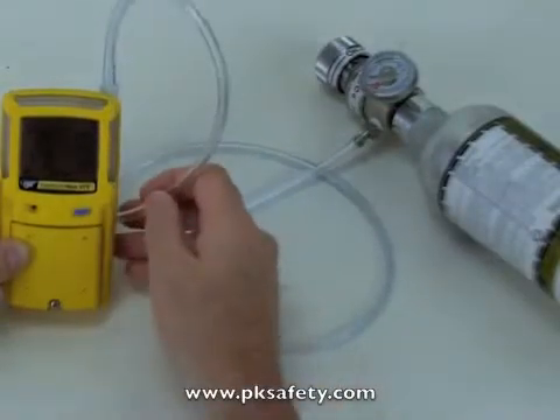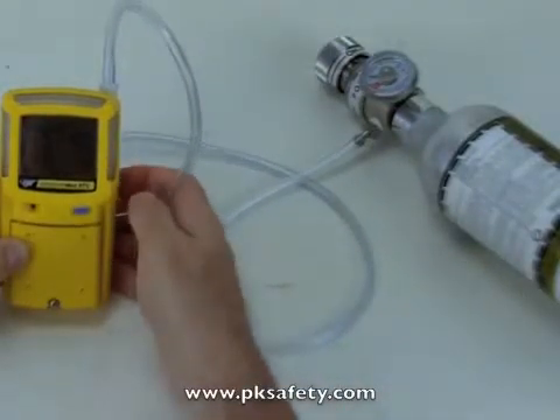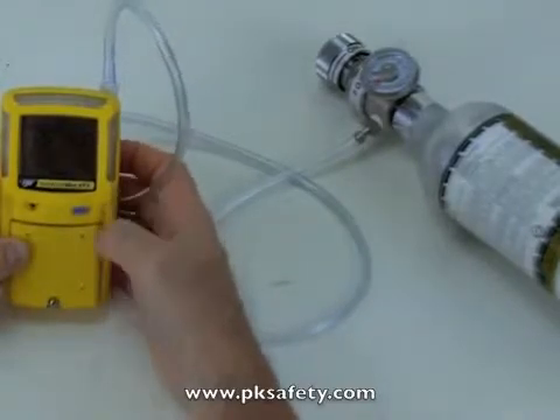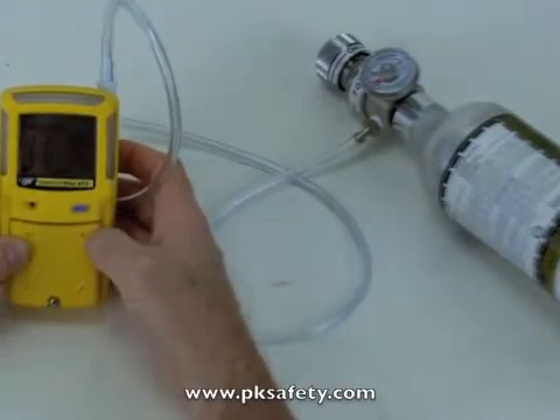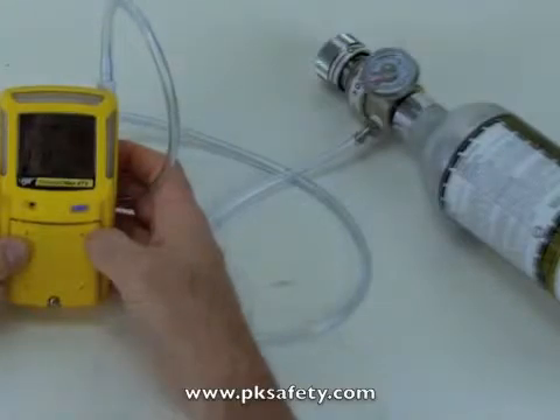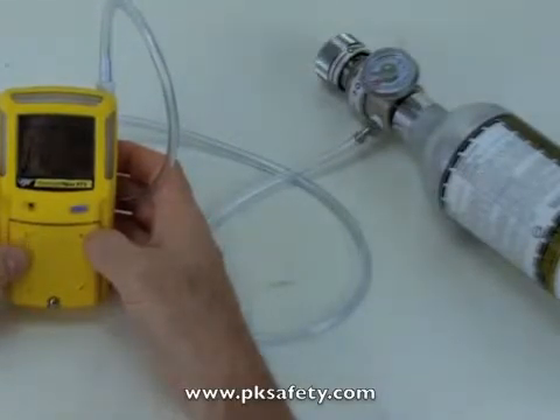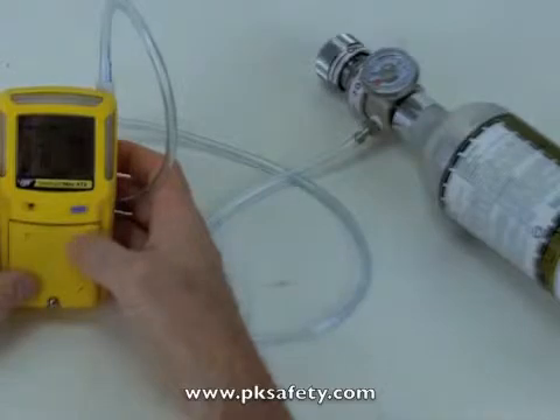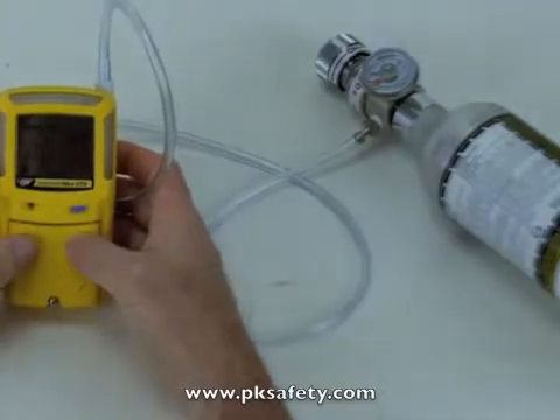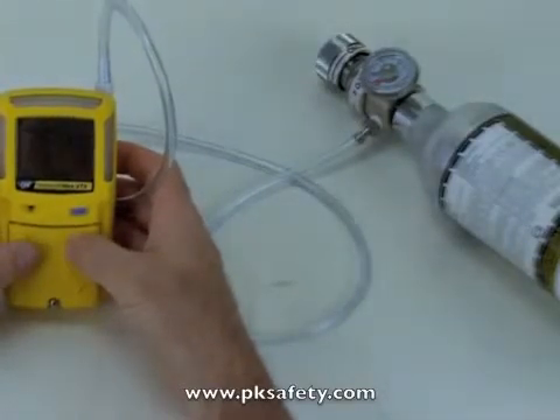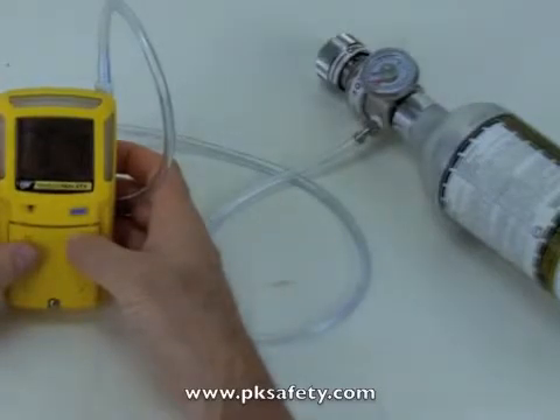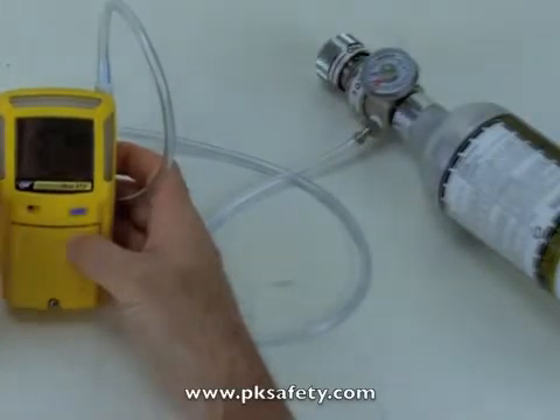Now, calibration is kind of an interesting thing. OSHA, if you follow the rules exactly, I think would have you calibrate this unit every day. Most of our utility customers, that is people who use these things day in and day out, they may go for a week or even a month. But if you're the type of user that only fires up the instrument occasionally, let's say once a month or something like that for a job, I would suggest that you strongly consider calibrating it every time. This is a life-saving instrument, and really the only way to know that it's working appropriately is by putting cal gas across the unit.